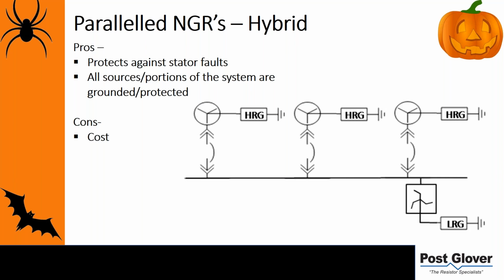So you have an HRG per generator, typically 5 or 10 amps really, depending on how you want to size it. And honestly, for this scenario, the only thing you really need to worry about is sizing. Because usually, when you have high resistance ground systems, you're worried about capacitive charging currents. In this scenario, you really only have to worry about that of the generator, which is not very much at all. So it's not really an issue typically, but a common size would be 5 or 10 amps regardless. But anyway, you have an HRG per generator. You still have the derived neutral off of the bus, and then therefore you have an LRG here.